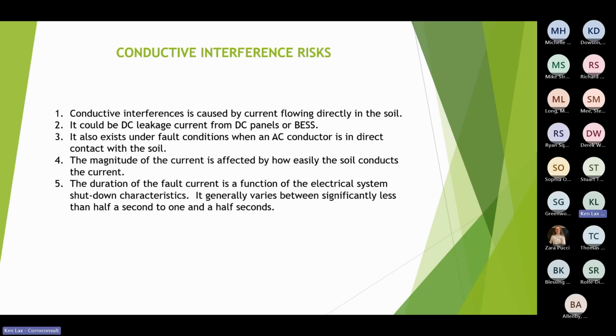The AC systems, on the other hand, the predominant mechanism is inductive, but when there's a fault between one of the phases and the earth, you get the current flowing in the earth, and these currents are usually quite high. It's not unusual to look at substation fault currents of 35,000 amps. The good news is it doesn't last very long. It automatically shuts down and does all kinds of clever stuff. And it varies how long it takes to shut down. Modern systems, about 0.2 of a second. Older systems could be up to 1.5 seconds.